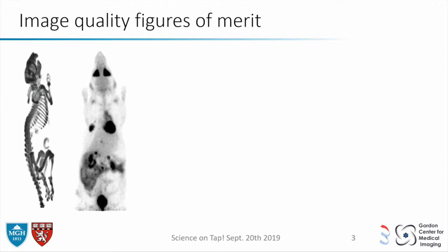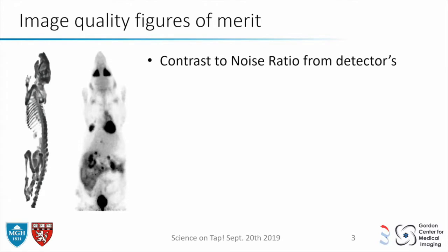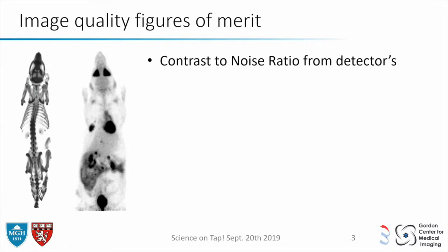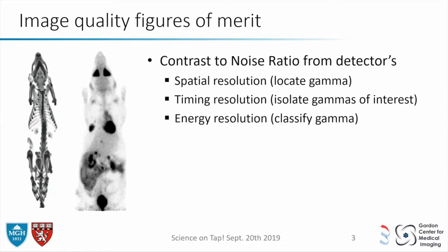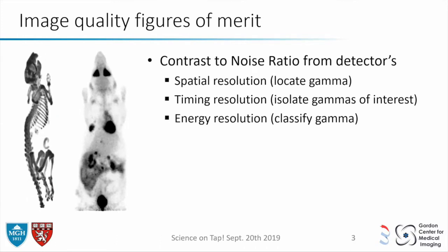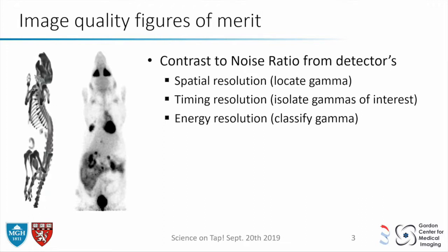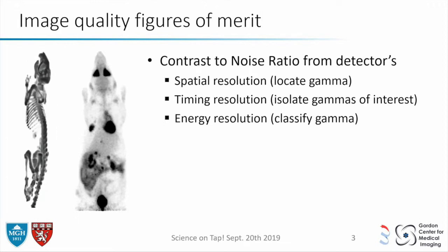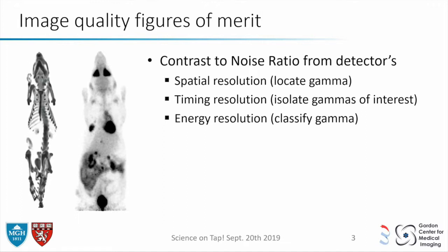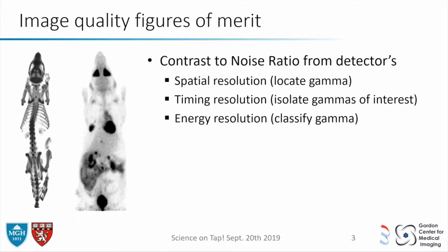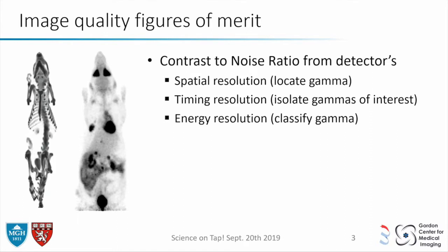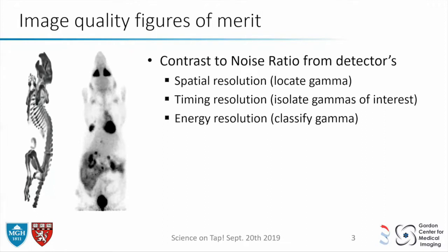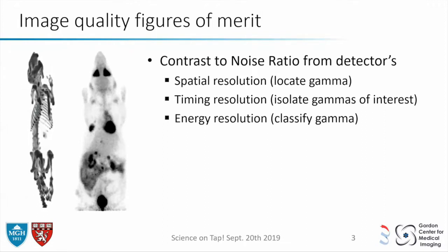To know if you can do that properly, you need to have good images with good contrast, to make sure you can see the difference between something that's healthy, something that's not, or something that's just not responding. To do that you need three things from the instrument. You need good spatial resolution so you can locate where the line came from. You need good timing resolution so you can pair up events correctly and throw out noisy data. And you need good energy resolution, which allows you to classify detections.